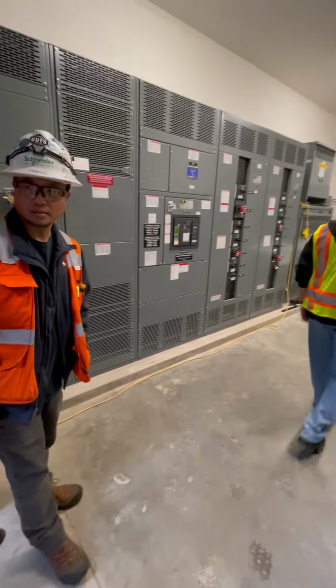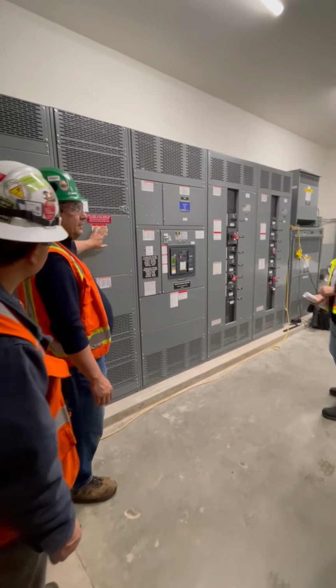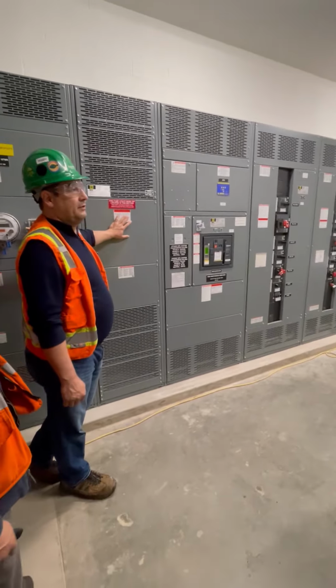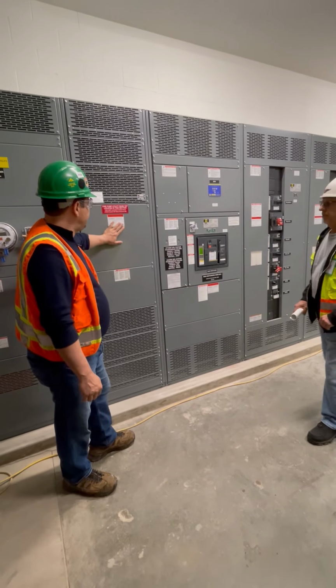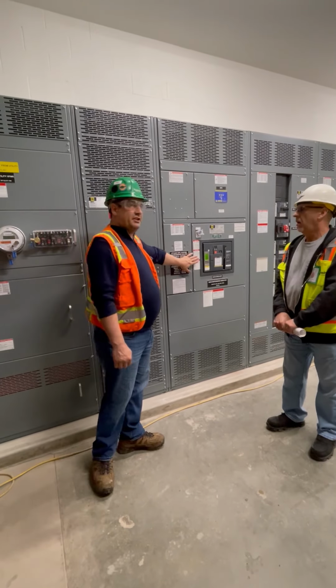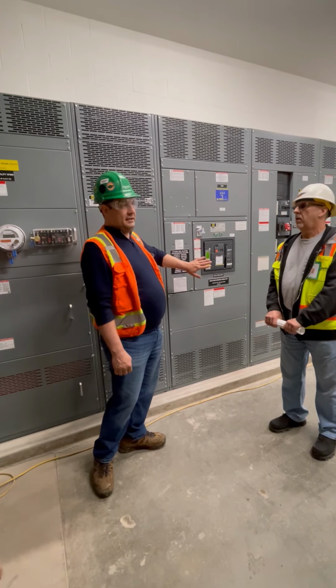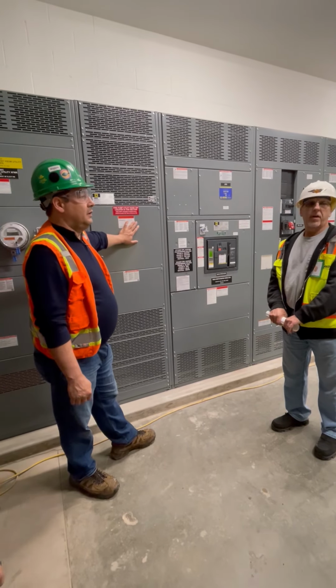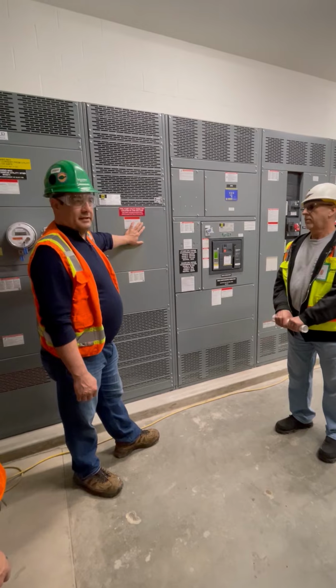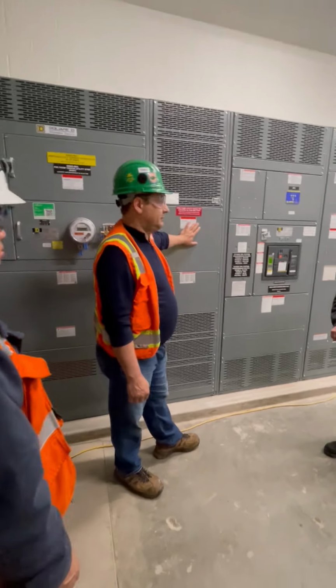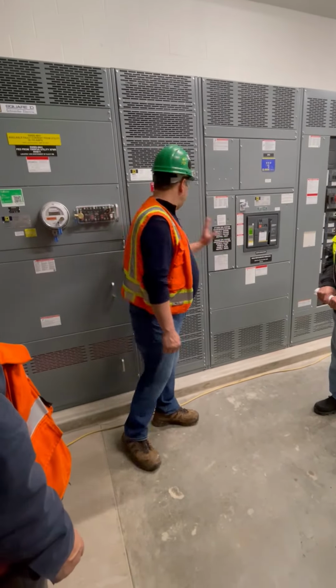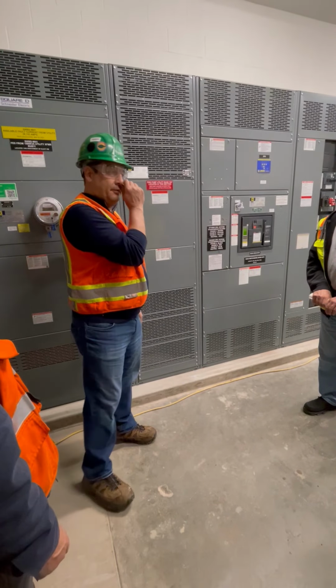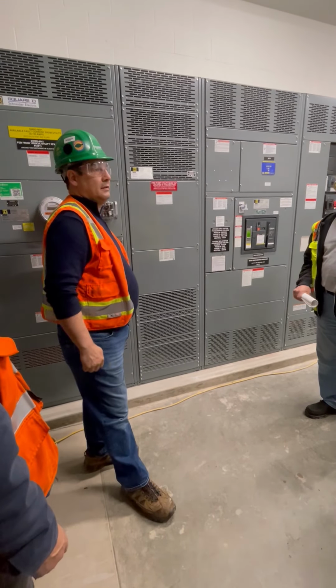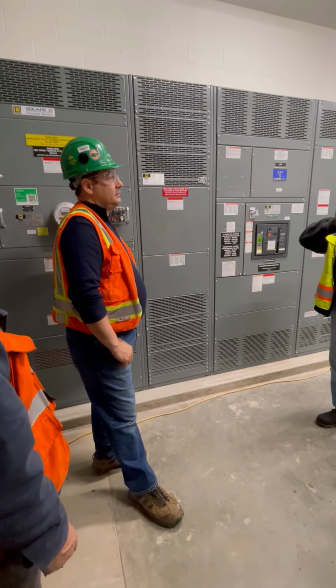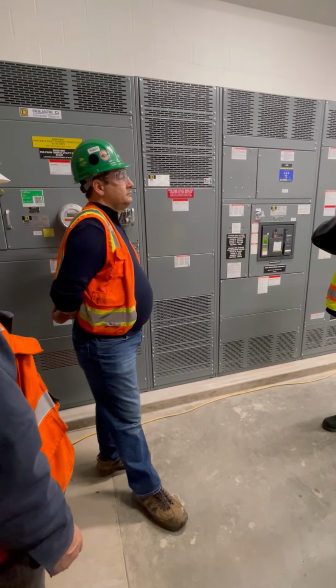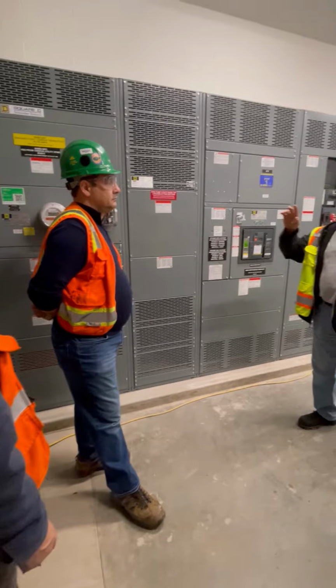On this switchboard, I just noticed you have a fire pump, so you obviously have a fire pump in the building, right? This fire pump is before this breaker, so it's not protected by anything. No, it's designed on purpose to run until it burns down in case of a fire. So that's why it's here. You can't turn the fire pump off. I noticed when they did it the first time, they'll explain that to us.